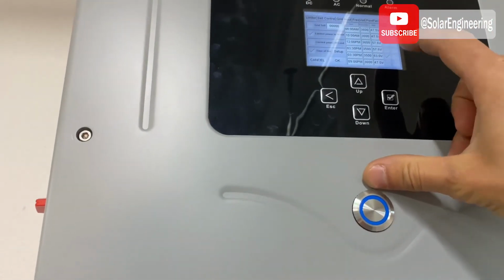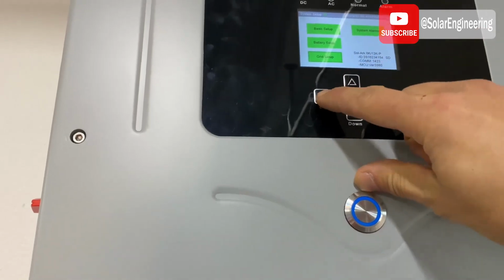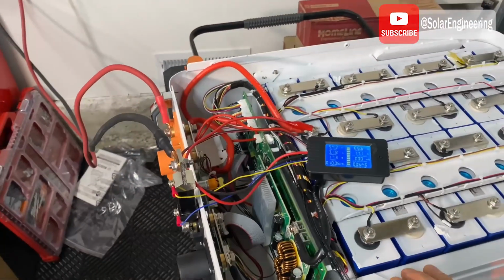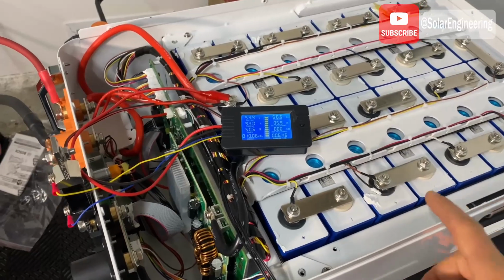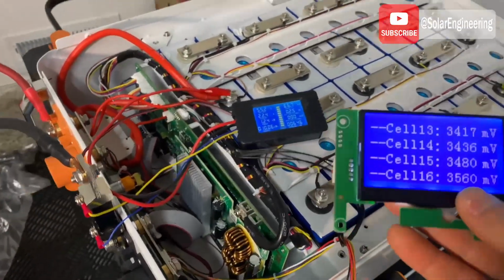So I'm going to enable the inverter to charge the battery with 20 amps, and the charging voltage is 57.6 volts per specification for this pack, which is 3.6 volts per cell. We're charging with 22 amps and the voltage is 55.1 volts.